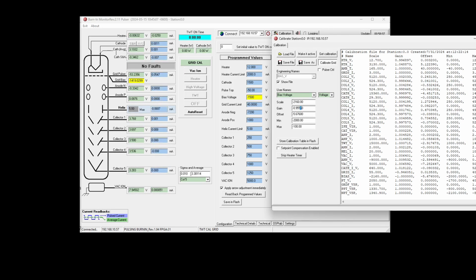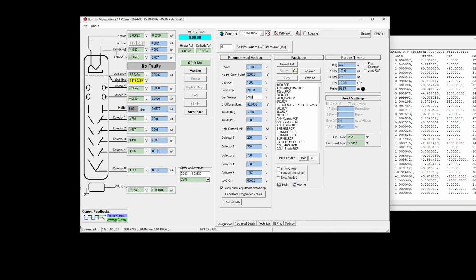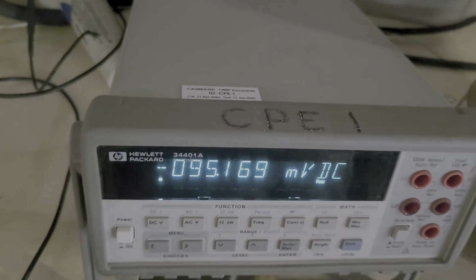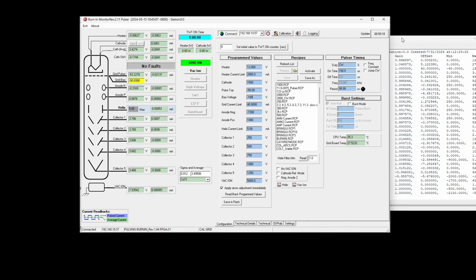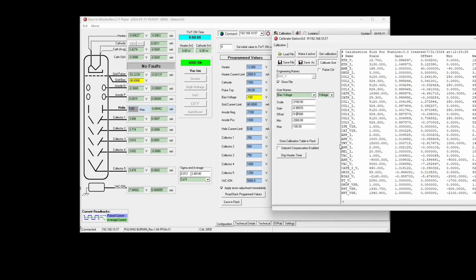Like so. Let's take this back down, and we're going to do successive approximation of about 3 iterations in order to get our 1419 and 95. Let's go see what that meter says. Still at 95.17, so the DAC has not caused any drift in the set point. 95.17, we have 1419.0. So we're going to readjust to read 95.17. Like so.